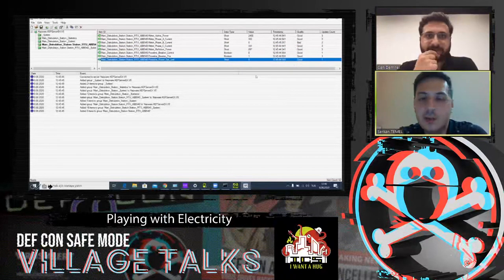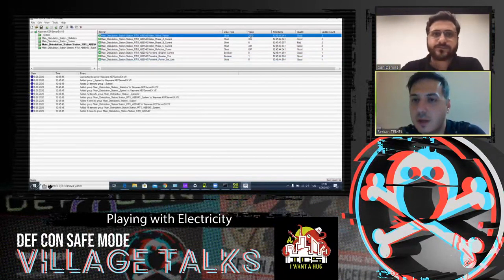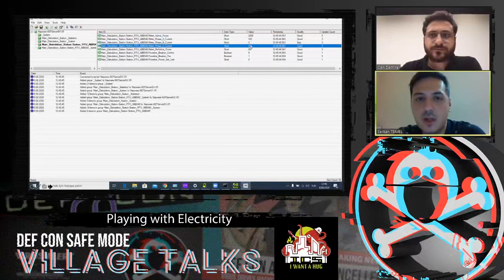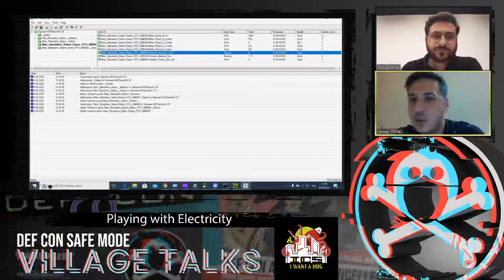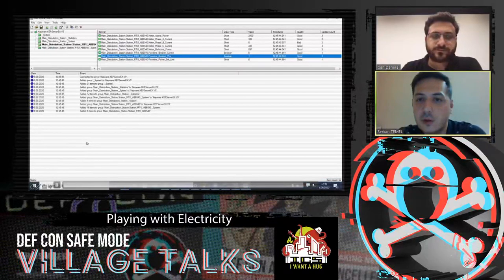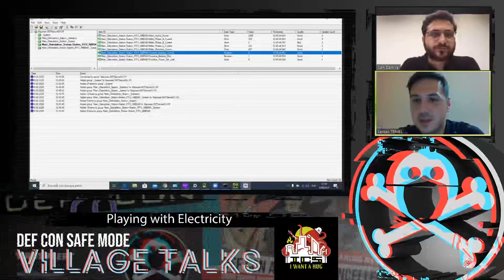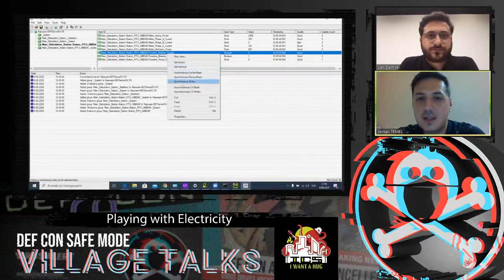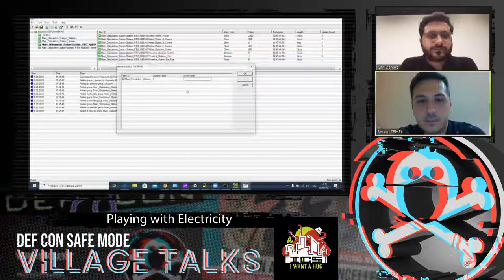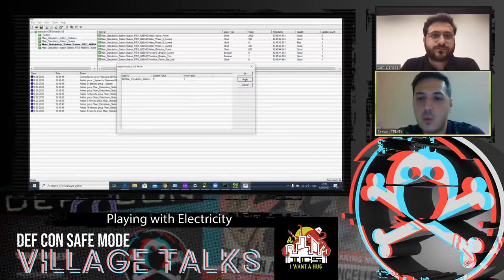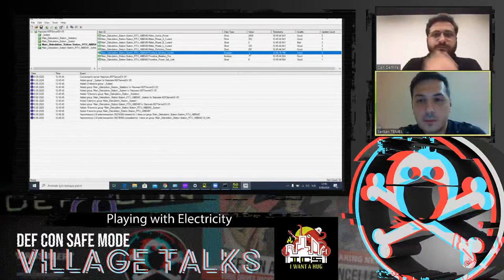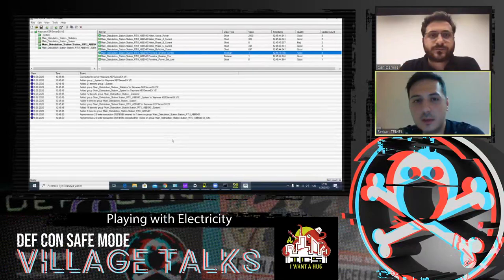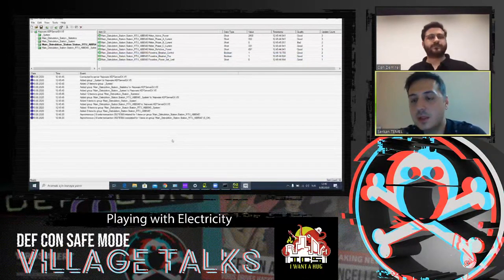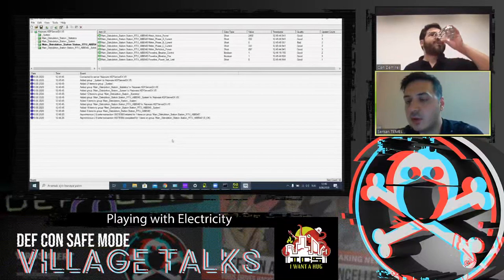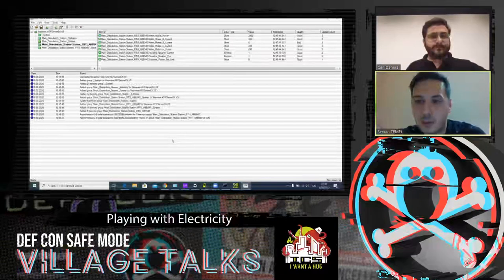Now we are connected to the RTU. As you see, this is the real-time data. Active power is 2400 and breaker control is zero. Breaker position is one, which means closed. Now we send the breaker control. The control command is one. Yes, it takes the command. In real-time operation, when we send this command, we re-energize the circuit breaker or shut down the circuit breaker.